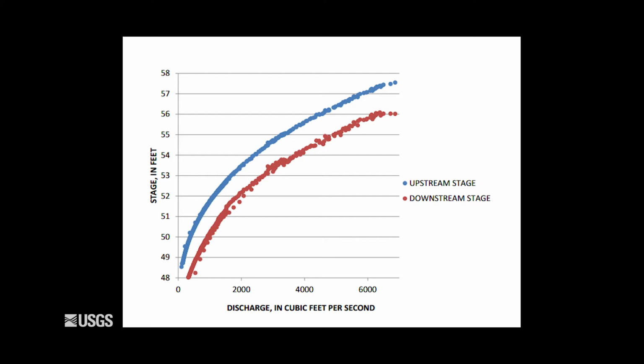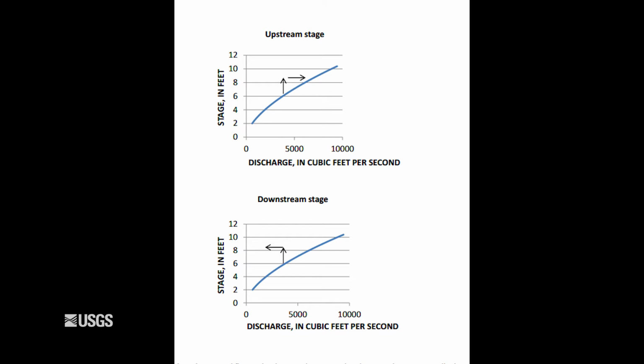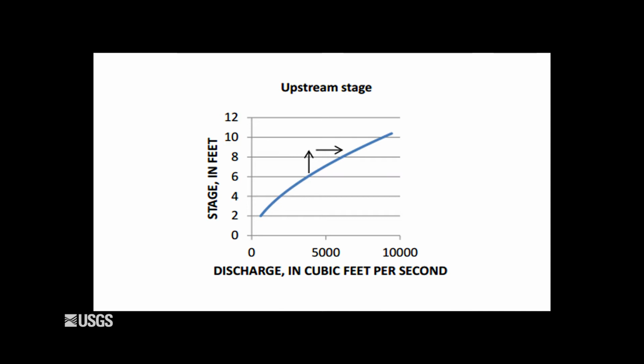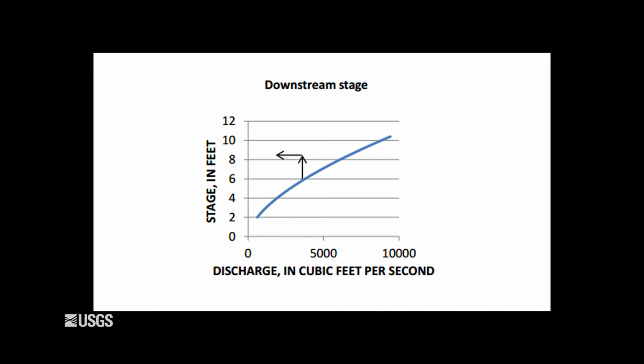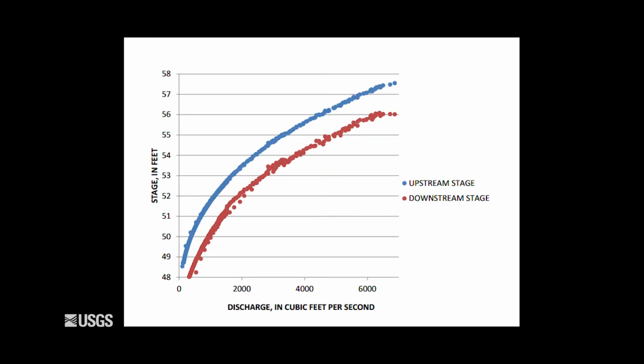And it turns out that there's actually a reason for this. It isn't just coincidence. And the reason for this is illustrated in these two plots. This is looking at the fluctuations in the upstream pressure transducer. If there's an upward tick in the stage, the slope is going to increase, which will increase the computed discharge. So the stage moves up and the discharge moves back towards the rating curve because the computed discharge is increasing too. Whereas if there's an upward tick in the stage of the downstream gauge, the stage goes up, but it's going to reduce the slope, and consequently the computed discharge is going to decrease and move away from the rating curve. So that's a likely explanation for why we're getting smoother rating curves using the upstream gauge.